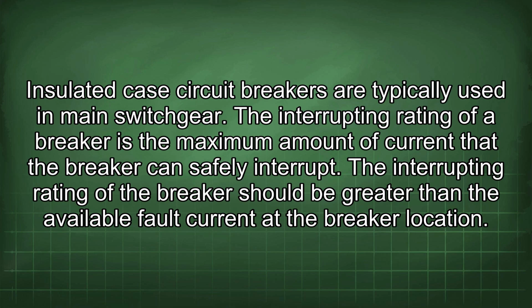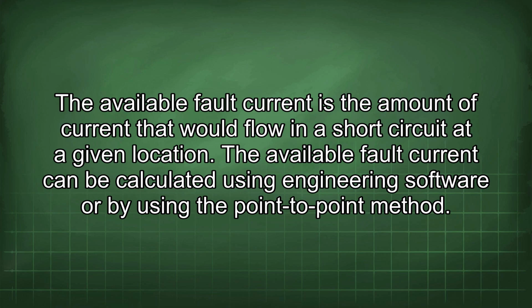The interrupting rating of a breaker is the maximum amount of current that the breaker can safely interrupt. The interrupting rating of the breaker should be greater than the available fault current at the breaker location. The available fault current is the amount of current that would flow in a short circuit at a given location. The available fault current can be calculated using engineering software or by using the point-to-point method.